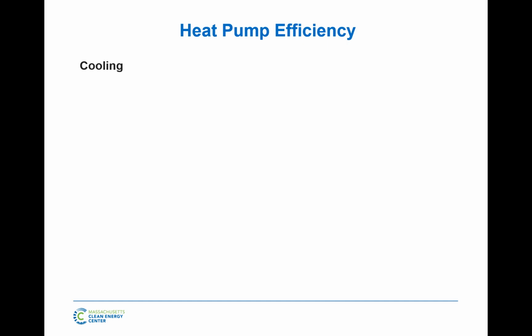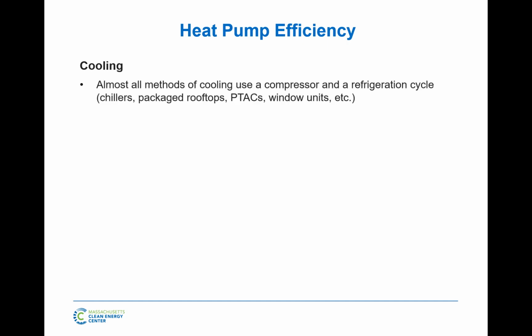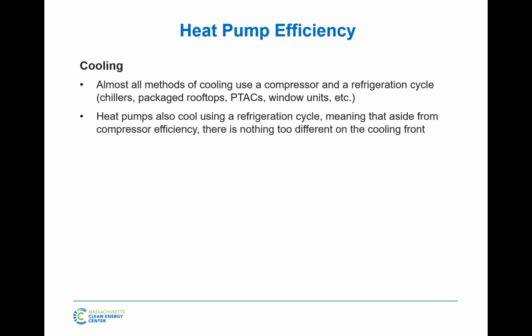Let's talk about efficiency a little bit, and I'm going to break it down looking at the cooling side of things. Basically, almost all methods of cooling in the world, no matter what system you're using, at some point in the system use a compressor, a refrigeration cycle. Whether it's a chiller, even a geothermal system uses a compressor, because the water source heat pumps use compressors. So they all use a certain version of the refrigeration cycle. Air source heat pumps also do that, but again, they use that in heating as well.